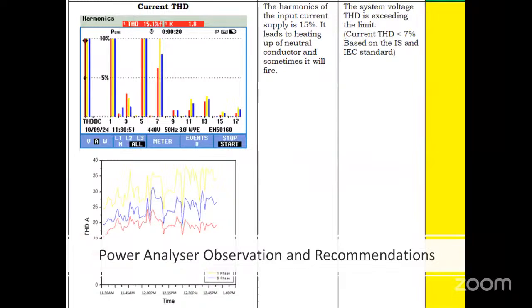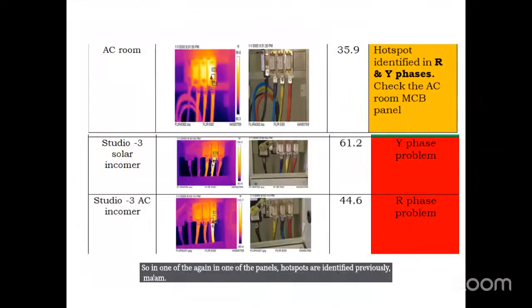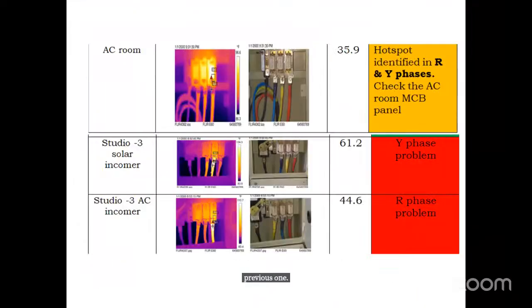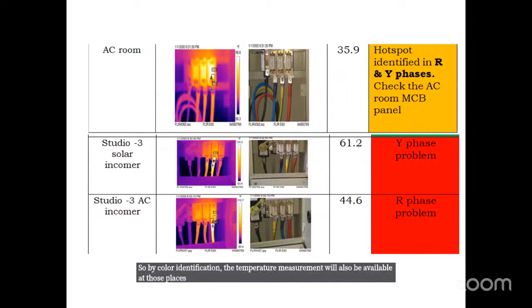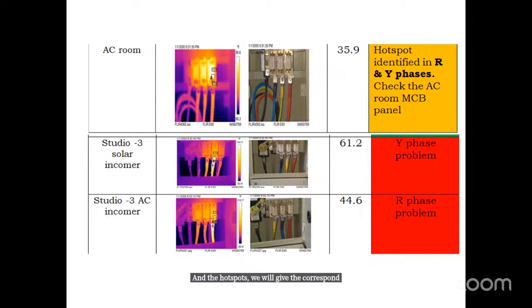In one of the panels, hotspots are identified, in two of their phases. In the second and third, we could see problems in the Y phase and R phase. By color identification, the temperature measurement will also be available at those places. We note down the temperature, and based on the temperature and hotspots, we give the corresponding recommendation and observation.